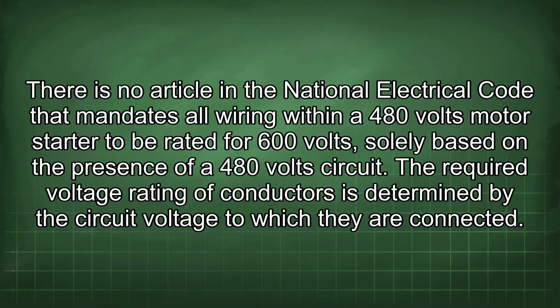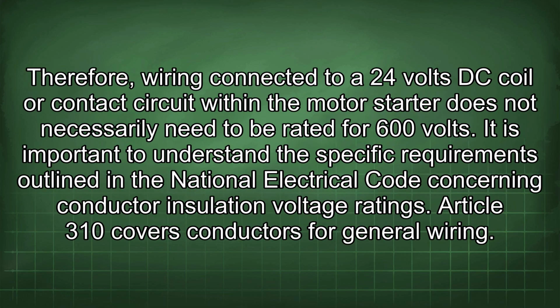There is no article in the National Electrical Code that mandates all wiring within a 480 volt motor starter to be rated for 600 volts solely based on the presence of a 480 volt circuit. The required voltage rating of conductors is determined by the circuit voltage to which they are connected. Therefore, wiring connected to a 24 volt DC coil or contact circuit within the motor starter does not necessarily need to be rated for 600 volts.